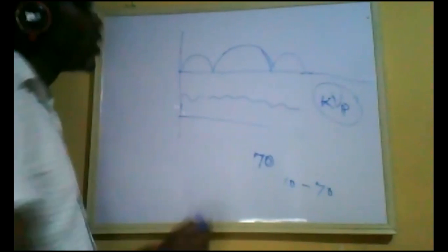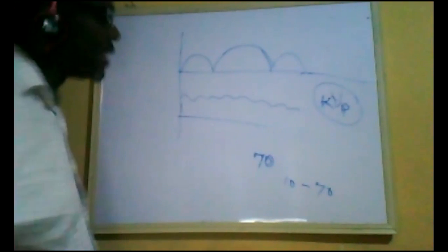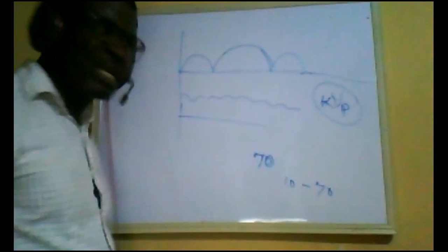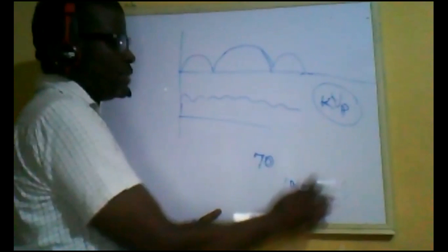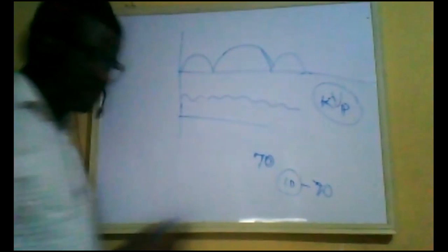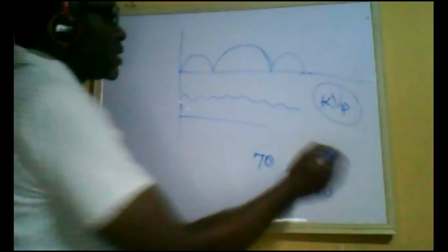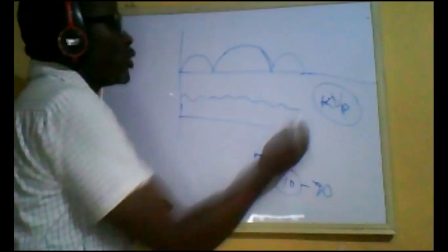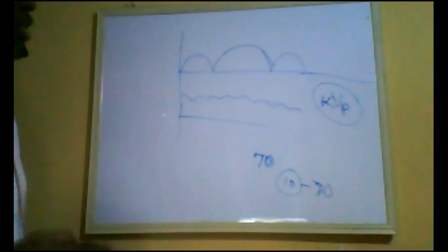So what this does in radiography is that ripple brings about so many impurities, that is, so many voltages. Because of that, we use filters to filter off the smaller voltages, which wouldn't help in image contrast. These lower voltages constitute patient dose.